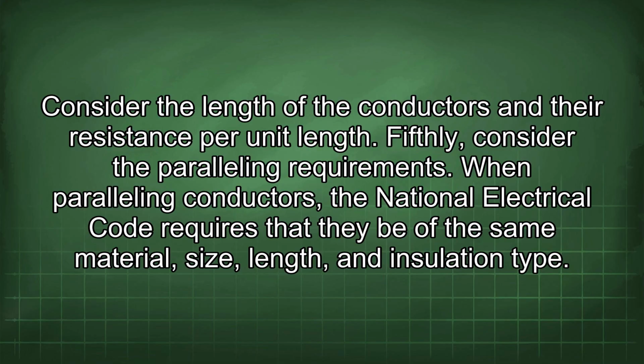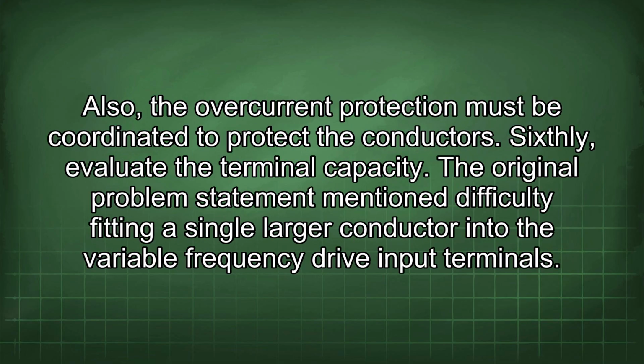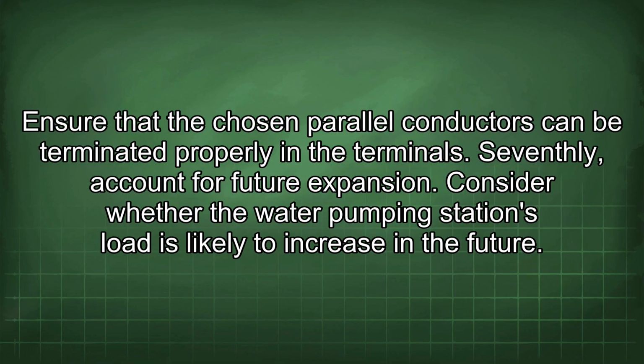Fifthly, consider the paralleling requirements. When paralleling conductors, the National Electrical Code requires that they be of the same material, size, length, and insulation type. Also, the overcurrent protection must be coordinated to protect the conductors. Sixthly, evaluate the terminal capacity. The original problem statement mentioned difficulty fitting a single larger conductor into the variable frequency drive input terminals. Ensure that the chosen parallel conductors can be terminated properly in the terminals.